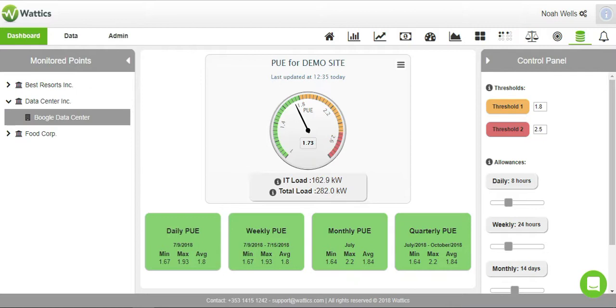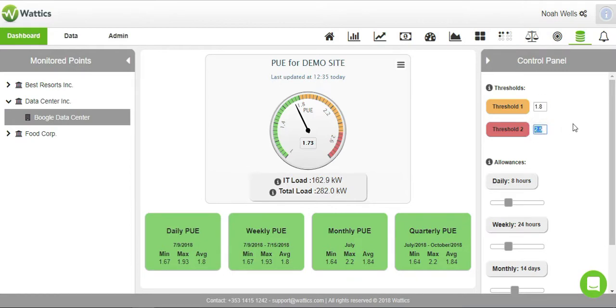The ideal PUE for maximum efficiency is 1, and it is preferred to stay between 1 and 2. On the right-hand side are the indicated thresholds. If you want to be notified when the PUE exceeds 1.8 or 2.5, you have an orange and red notification setting.